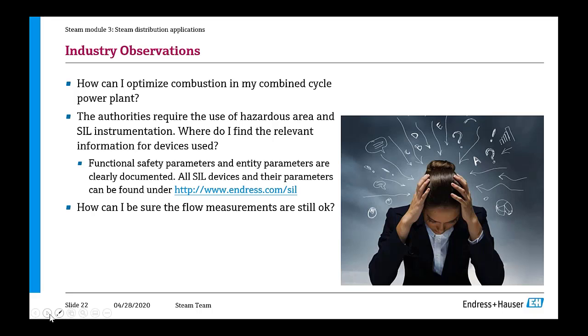Then we said the authorities require the use of hazardous area and SIL instrumentation. Where do I find the relevant information for devices used? Especially for the functional safety parameters, this is very easy. These parameters can be found under endress.com/sil. So all devices that have IEC 61508 or are suitable for SIL 2, SIL 3, they have got this FMEDA, the documentation of the safety relevant parameters. And for hazardous area devices, of course, we have all the entity parameters documented.